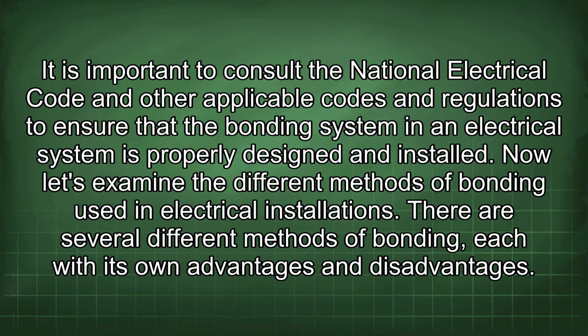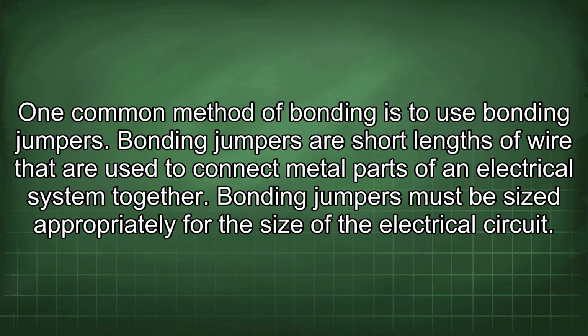Now let's examine the different methods of bonding used in electrical installations. There are several different methods of bonding, each with its own advantages and disadvantages. One common method of bonding is to use bonding jumpers. Bonding jumpers are short lengths of wire that are used to connect metal parts of an electrical system together. Bonding jumpers must be sized appropriately for the size of the electrical circuit.